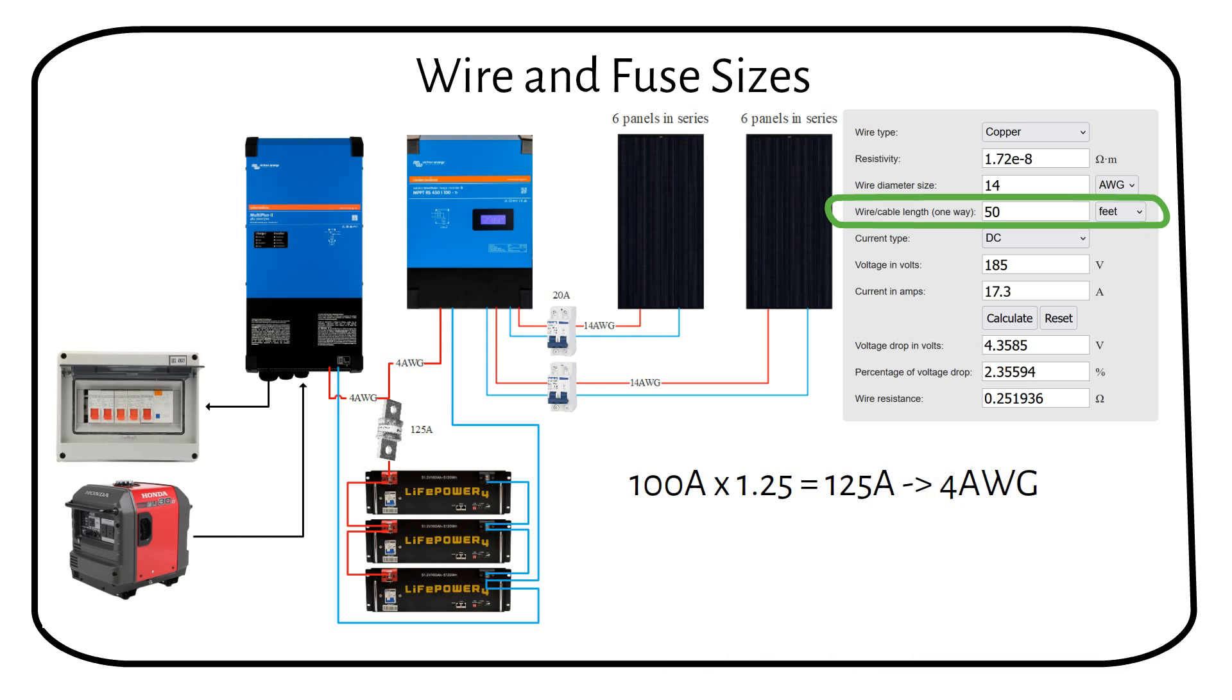The charge controller outputs 100A. Applying a 1.25 safety factor, you would need a cable that can handle 125A. Use 4 gauge welding cable, which can carry up to 150A. Install a 125A class D fuse to protect the cable.